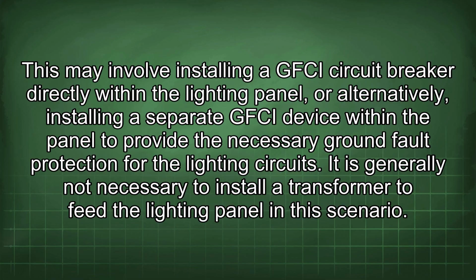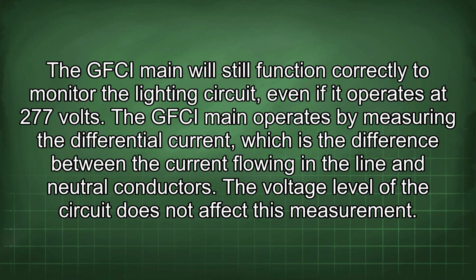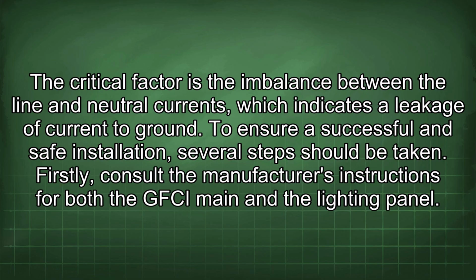It is generally not necessary to install a transformer to feed the lighting panel in this scenario. The GFCI main will still function correctly to monitor the lighting circuit, even if it operates at 277 volts. The GFCI main operates by measuring the differential current, which is the difference between the current flowing in the line and neutral conductors. The voltage level of the circuit does not affect this measurement. The critical factor is the imbalance between the line and neutral currents, which indicates the leakage of current to ground.